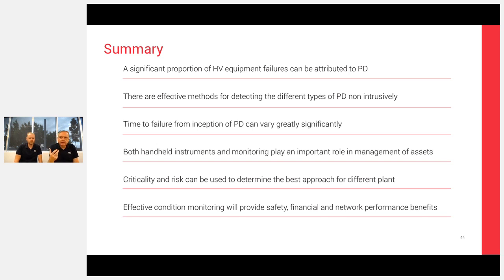On the switchgear that we saw failed in the UK, the biggest cause of the failure was typically tracking on the circuit breaker. So you would be pointing towards the spouts in that particular instance. So how and where we place the sensors is dictated to a certain extent by the type of switchgear, and that's where we usually have knowledge of that.